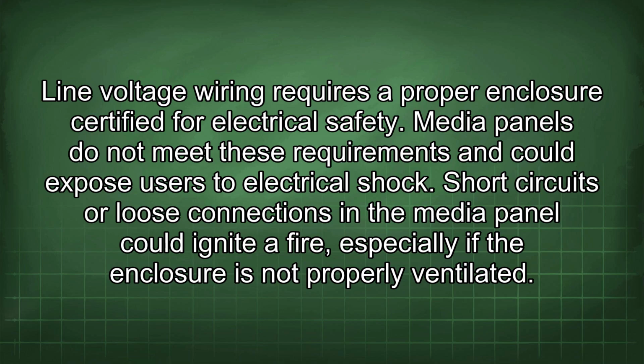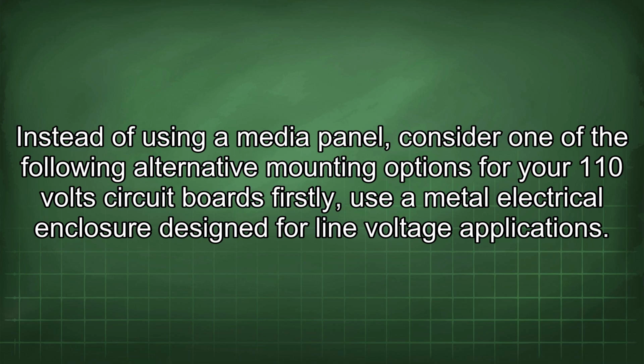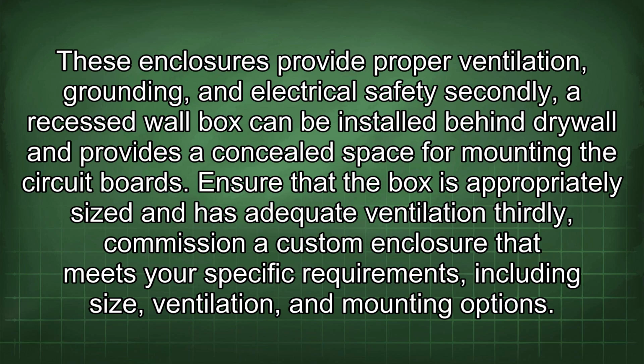Short circuits or loose connections in the media panel could ignite a fire, especially if the enclosure is not properly ventilated. Instead of using a media panel, consider one of the following alternative mounting options for your 110-volt circuit boards. Firstly, use a metal electrical enclosure designed for line voltage applications. These enclosures provide proper ventilation, grounding, and electrical safety.